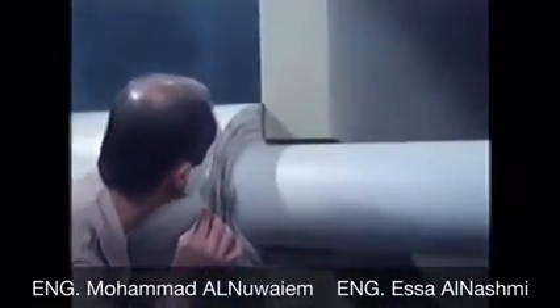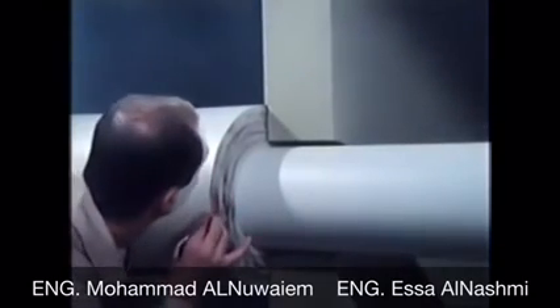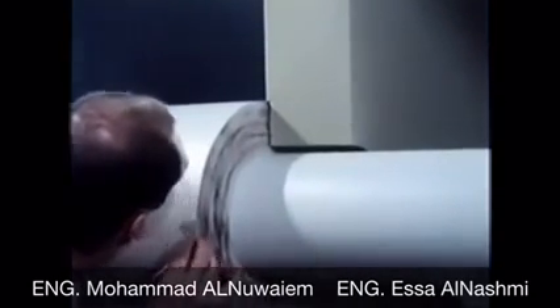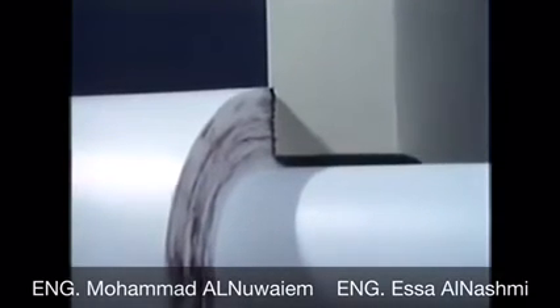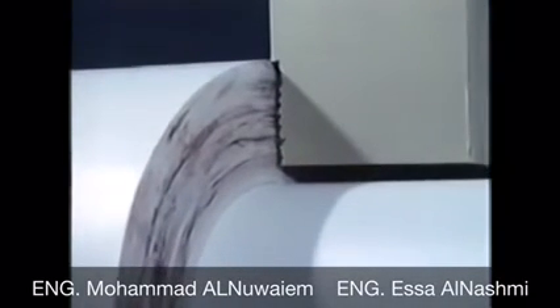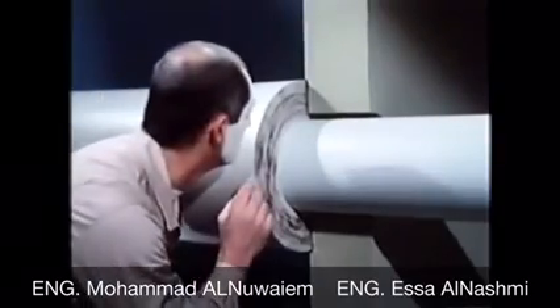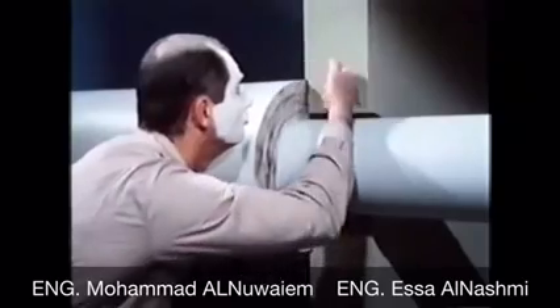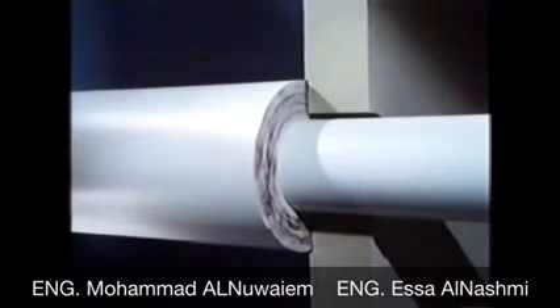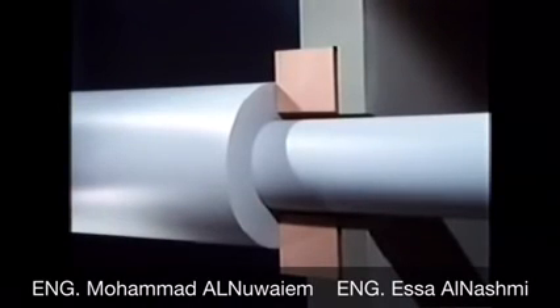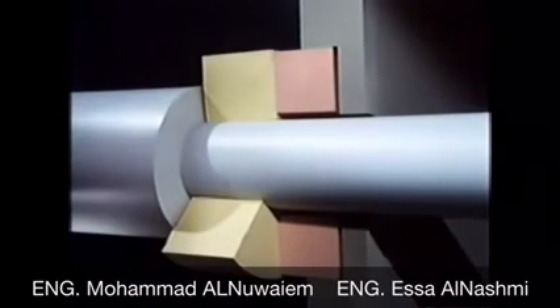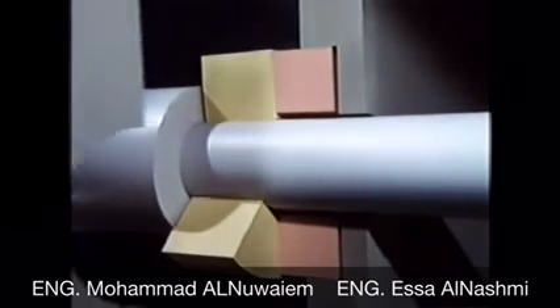The seal starts leaking due to wear caused by friction. The shaft and housing are far too expensive to be used as wearing parts. Ideally, only the seal faces should be changed. A stationary seat at the housing, a seal face on the shaft. Exchangeable wearing parts make it possible to optimize the various available materials.